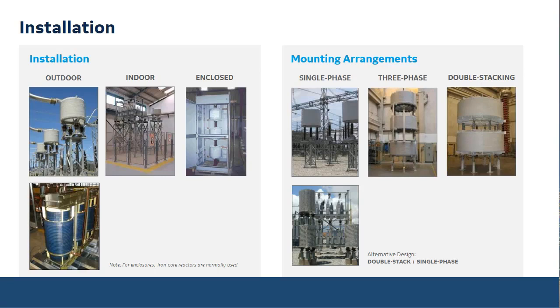Also, you may have issues with noise, especially for filter reactors. If there is a very high content of harmonics, the reactors can be very noisy. A typical reactor has a 55 to 60 dBA sound emission. A filter reactor may have 90, 100 dBA. So they can be very noisy. And the main concern with reactors is the magnetic field, and this is what I'm going to spend some time on in the next slides.